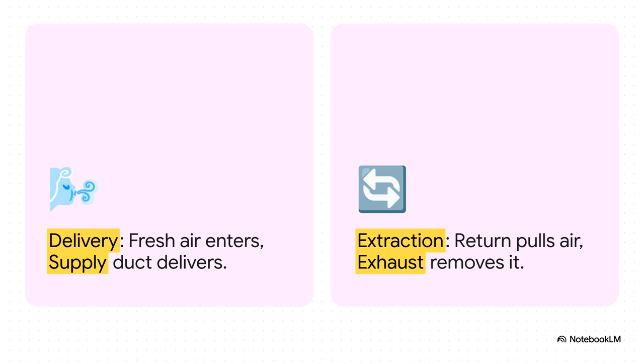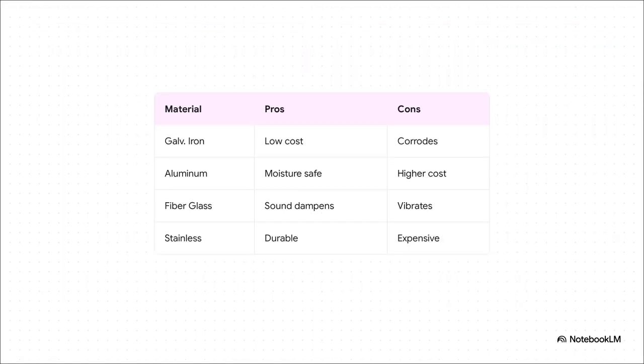On the delivery side, the fresh air duct, or FAD, pulls outside atmospheric air into the AHU. After conditioning, the supply air duct, or SAD, delivers that pristine air to the manufacturing areas. On the extraction side, the return air duct, or RAD, operates at a slight negative pressure to pull air from the rooms back to the AHU for retreatment. Finally, the exhaust air duct, or EAD, grabs heavily contaminated air from places like labs or toilets and vents it safely, directly outside. Now, choosing your ducting material is a real balancing act between safety and your budget.